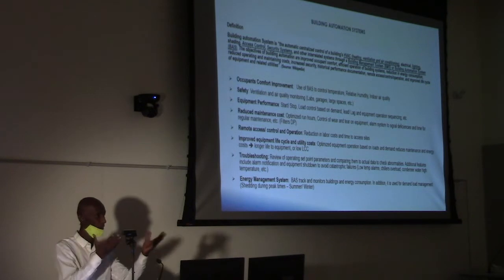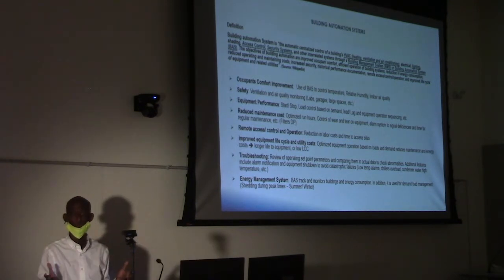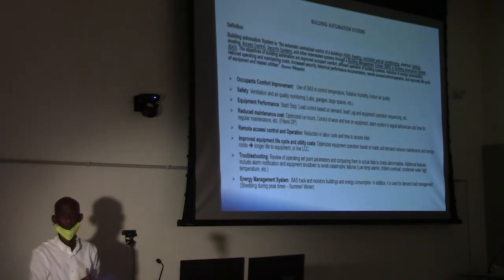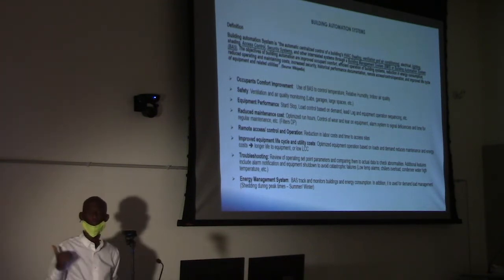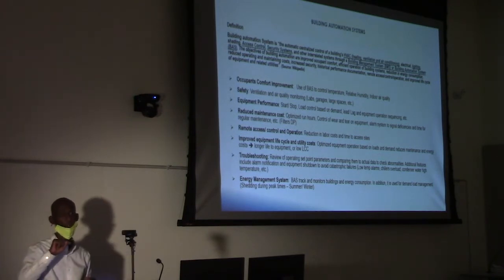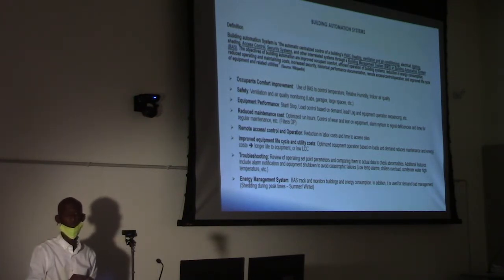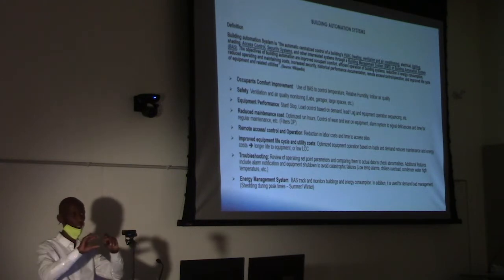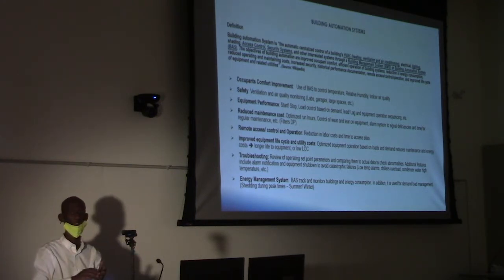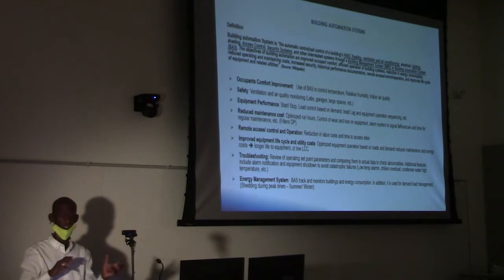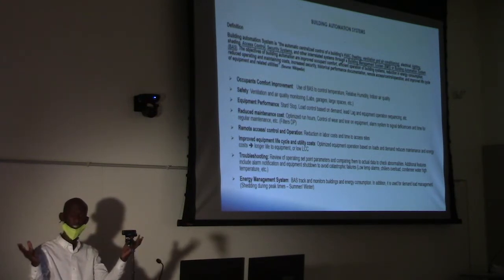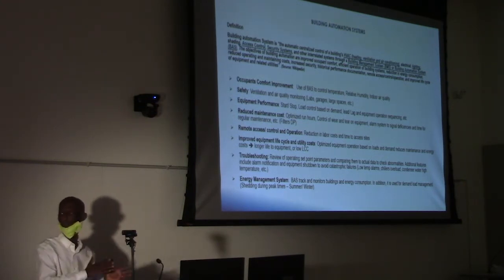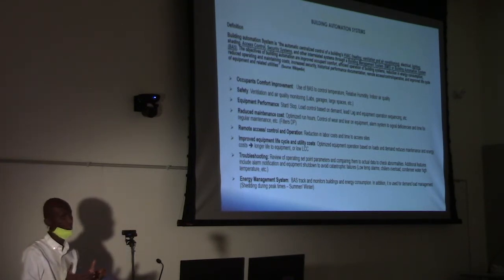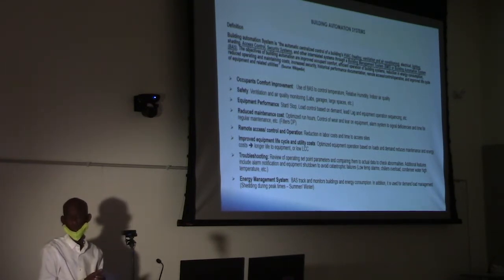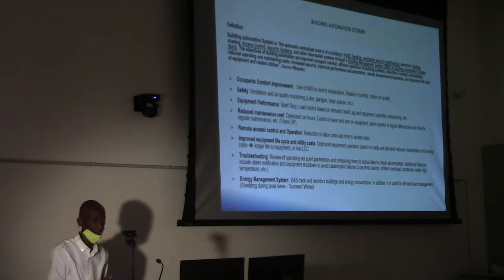when on Thursday, for instance, nobody was here. There were a few people. Okay, what we do is we turn off the equipment just by clicking on a point. We go and schedule units to be off. Okay, you maintain a certain temperature, let's say 60 degrees, instead of bringing outside air, heating and maintaining 70 degrees. So just by doing that for 60 buildings, you can save probably 20 to 30% of the energy consumption on campus.